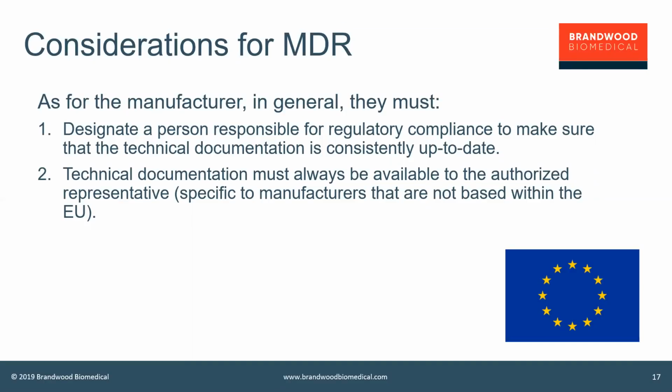So it is key, especially as a legal manufacturer outside of Europe, that your authorized rep holds enough information. Now, they don't have to have the whole technical file, and this is where it behooves manufacturers to have appropriate agreements in place with their authorized rep so that they can hold a subset or the full technical file to support any requests that come from the competent authority in an expedient manner.